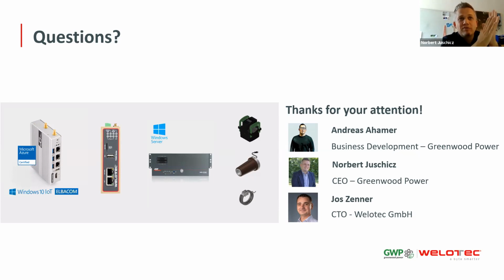You will fail if you install a voltage sensor with only class 1 accuracy and a device with an additional 2-3% inaccuracy, plus additional inaccuracy from cables and input impedance. So you end up with 5% inaccuracy, and then this use case makes no sense anymore. This must be considered during the first discussions, and then on top of this solution you can set up some of these algorithms.